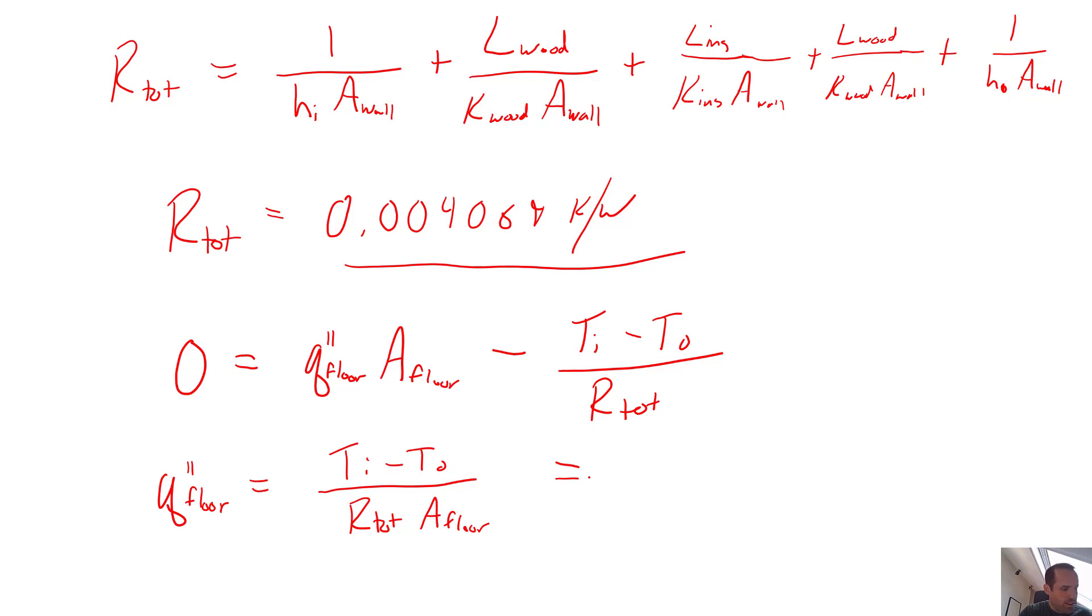So doing the math, again I did this offline, but we end up needing a floor heating system that can provide a flux of 86 watts per square meter. You can see the value of this thermal resistance method, you can see the value of just knowing about heat transfer to solve practical design and energy saving problems.